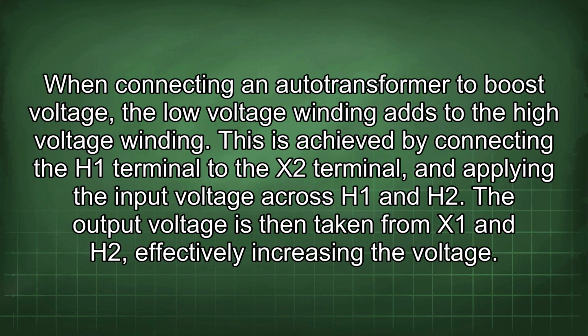When connecting an autotransformer to boost voltage, the low voltage winding adds to the high voltage winding. This is achieved by connecting the H1 terminal to the X2 terminal and applying the input voltage across H1 and H2. The output voltage is then taken from X1 and H2, effectively increasing the voltage.